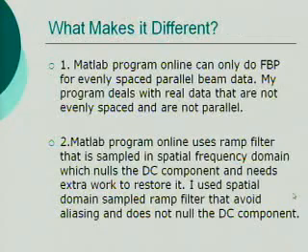So what makes my program different? There are some MATLAB programs online that can do filtered backprojection, but they can only do it for evenly spaced parallel beam data. But my program deals with real data that are not evenly spaced and are not parallel. And the MATLAB programs online use a ramp filter that is sampled in the spatial frequency domain, which loses the DC component and needs extra work to restore it. But I used a spatial domain sampled ramp filter that avoids aliasing and does not lose the DC component.